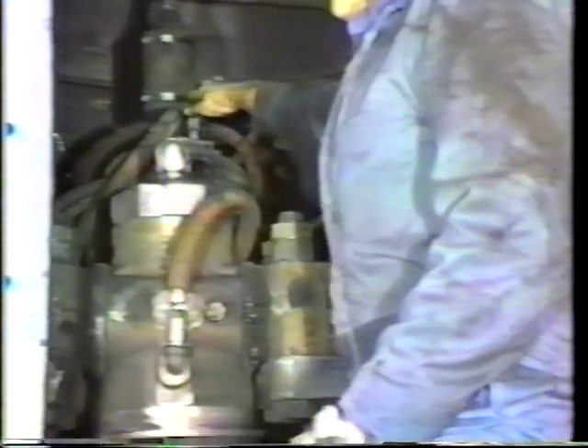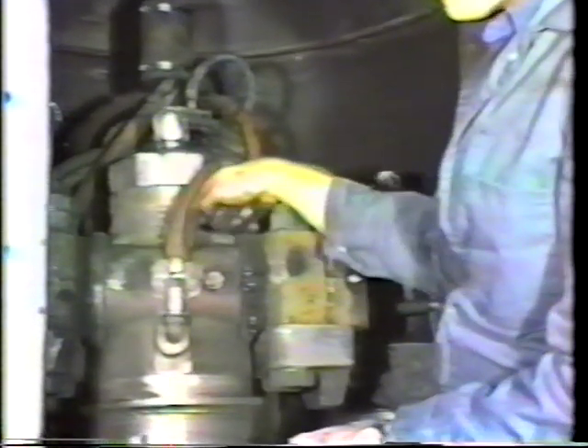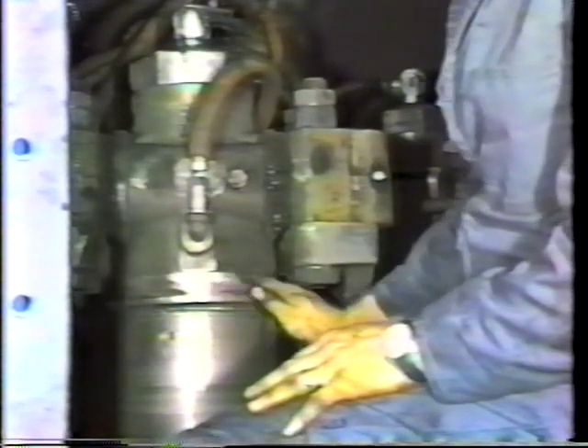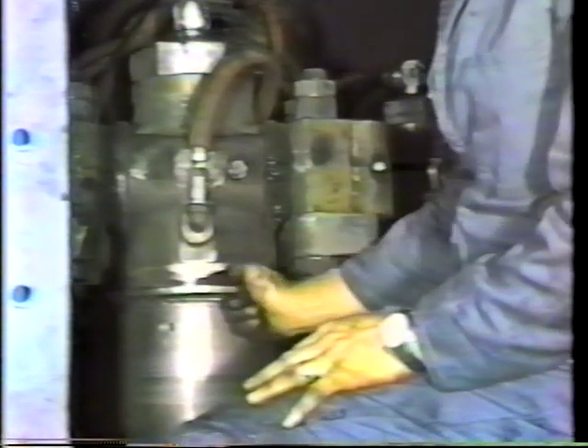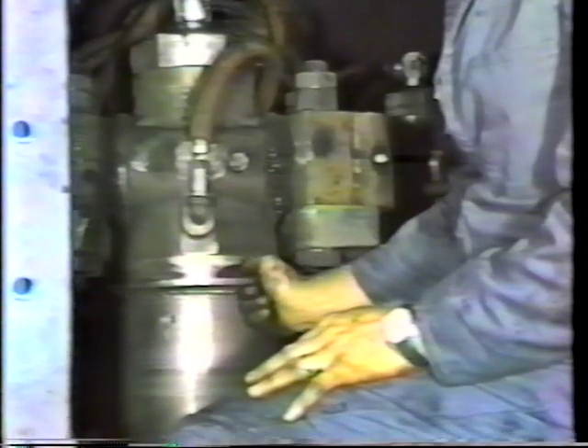Air also travels around the grease hose inside this pipe, comes down through behind the flexible hose and through a rotary air seal unit. The air then travels through these red hoses and enters into the journal via a check valve here and purges the seal area. And where does it exit? The air then exits from behind these swingers to blow the dust away from the seal area.